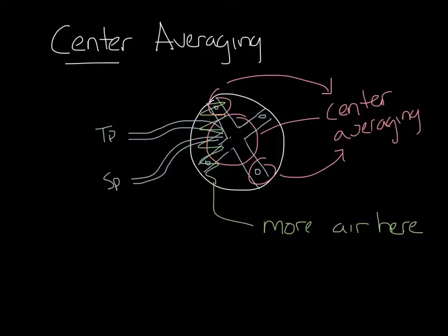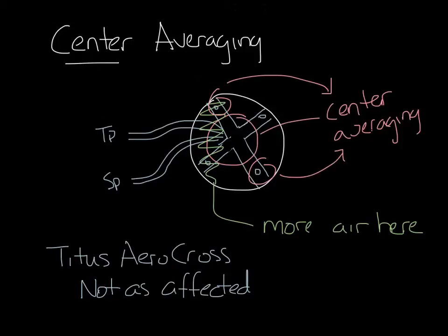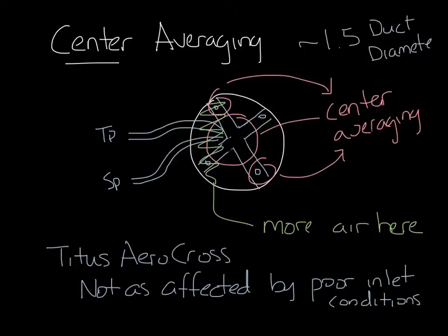This means that VAV boxes with center averaging flow sensors, like the Titus AeroCross, are not affected by poor inlet conditions as much as linear averaging sensors are. Because of this, you need less straight duct into the box inlet, about one and a half duct diameters for our flow sensor, compared to about three duct diameters for a linear averaging type sensor.